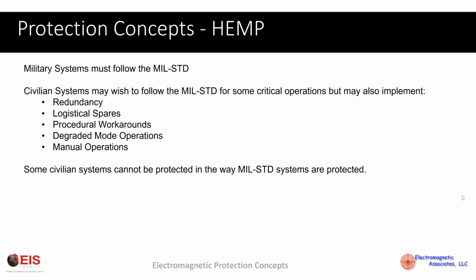So basically, when you're looking at protection concepts for military systems, it's pretty simple. You have to follow the MIL standard. There are a lot of organizations and support vendors to help comply with the MIL standard protection. And ultimately, the military looks at the mission of every single facility and decides whether the protection, as documented in test reports and other things, is sufficient.